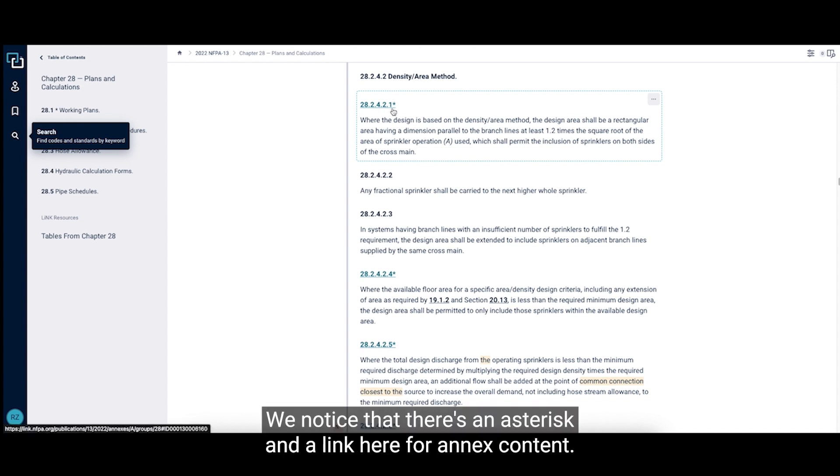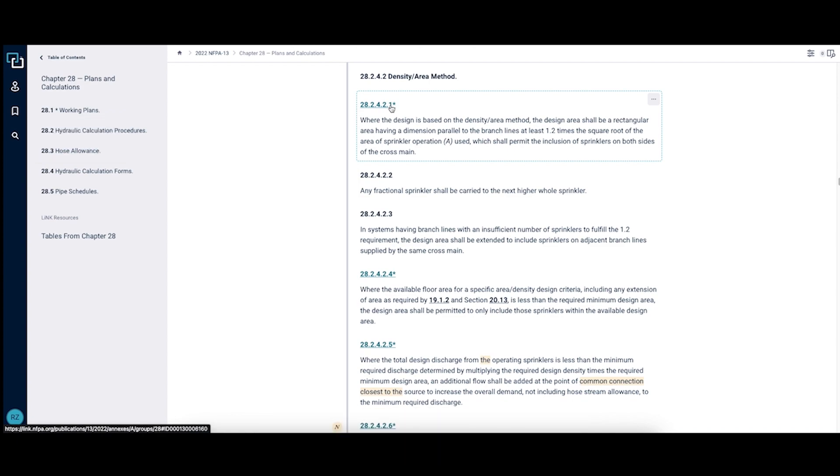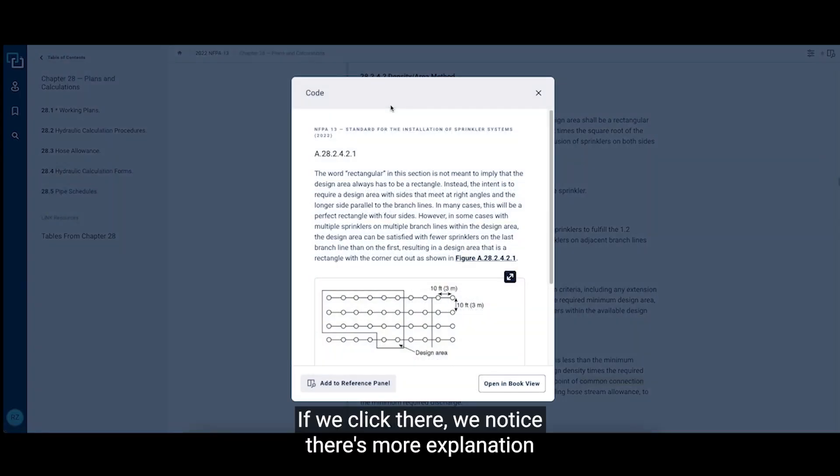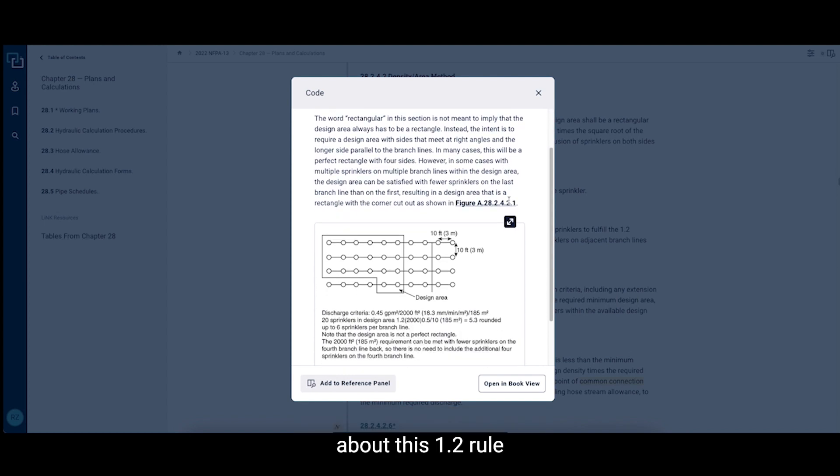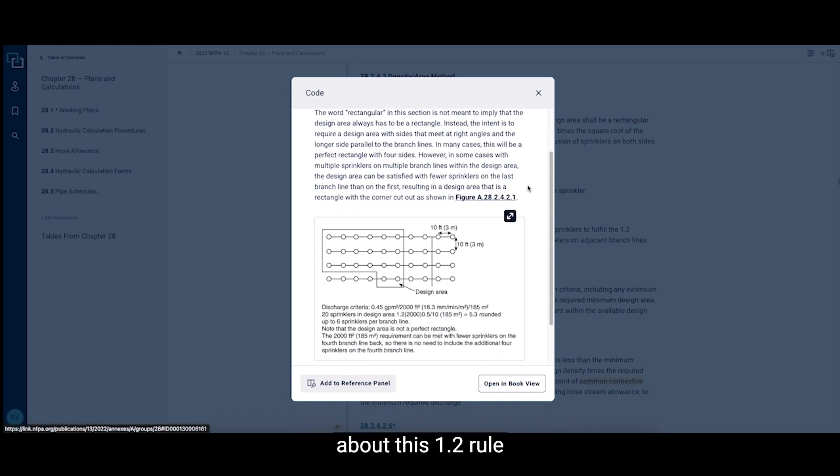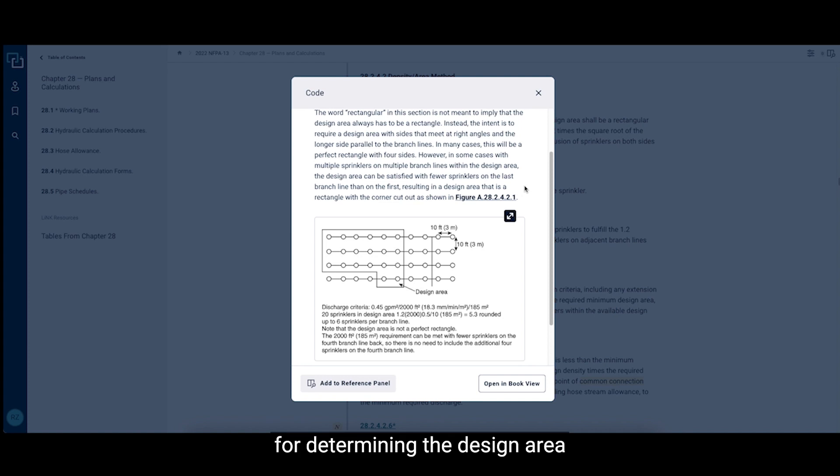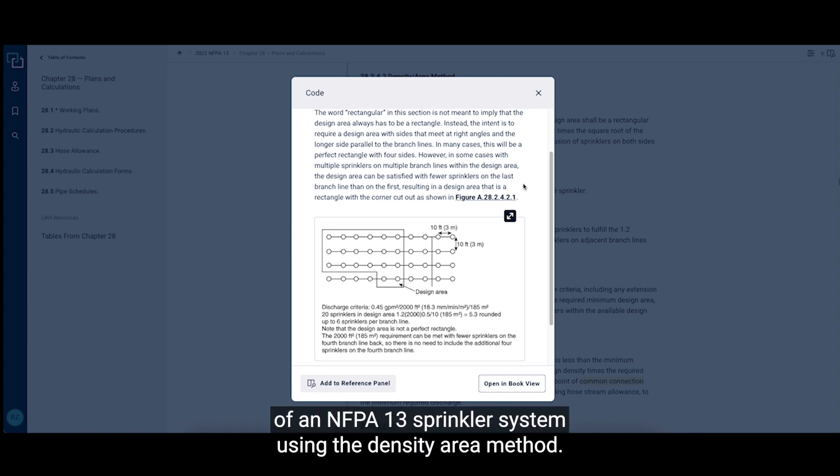We notice that there's an asterisk and a link here for annex content. If we click there, we notice there's more explanation about this 1.2 rule for determining the design area of an NFPA 13 sprinkler system using the density area method.